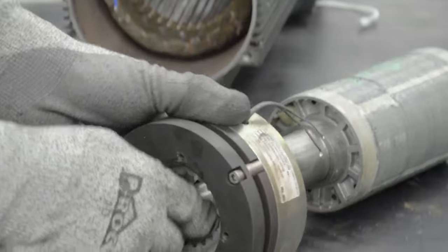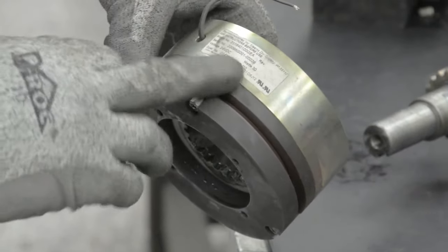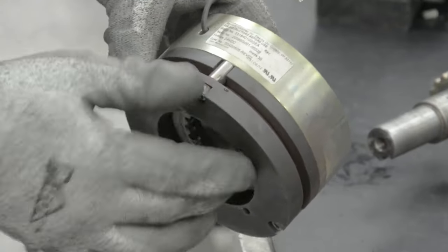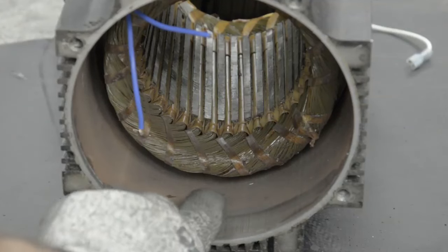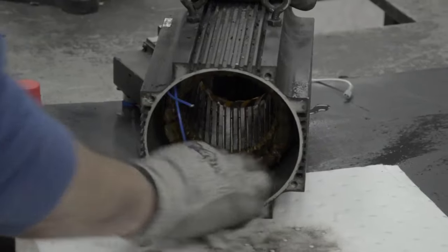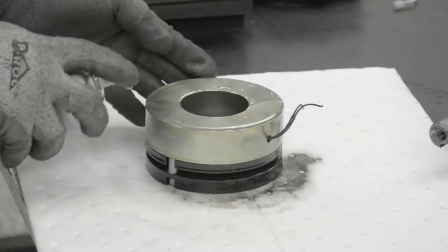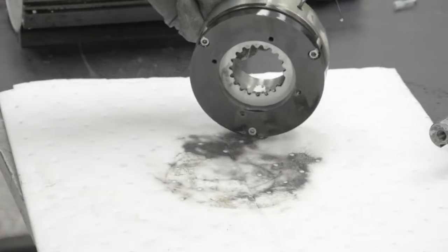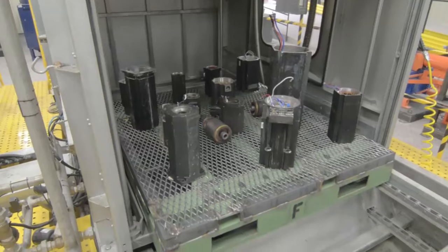Then we will remove the brake, which will need to be cleaned and re-verified after for its functionality. We can see the contamination inside the stator. And we'll remove the contamination. As we clean the brake, you can see all the dirt and contamination. We will get this motor into the alkaline washer to get all cleaned up.